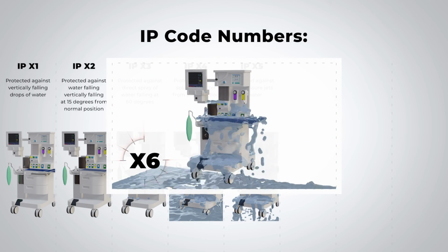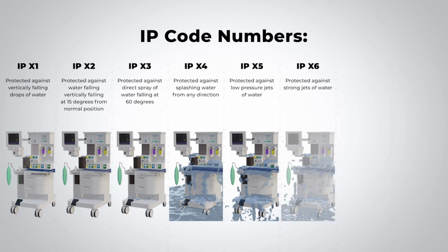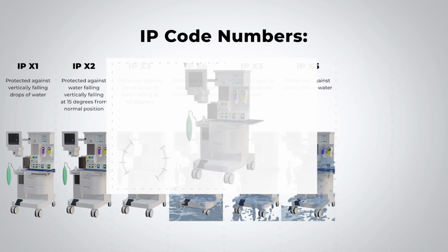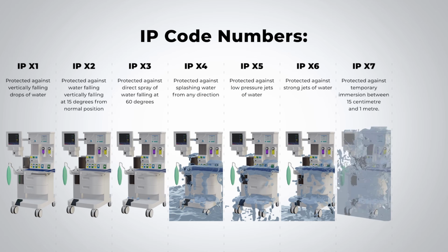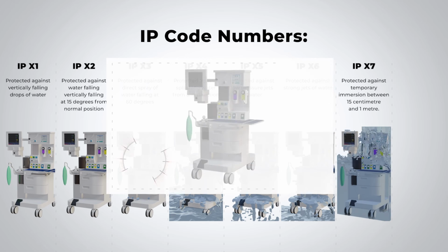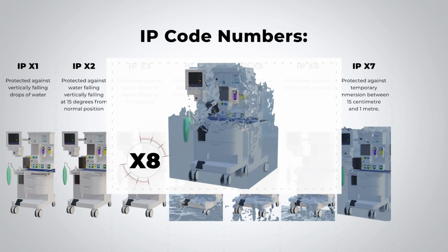6. Protected against strong jets of water. 7. Protected against temporary immersion between 15 centimeters and 1 meter. And 8. Protected against continuous immersion, waterproof beyond 1 meter.